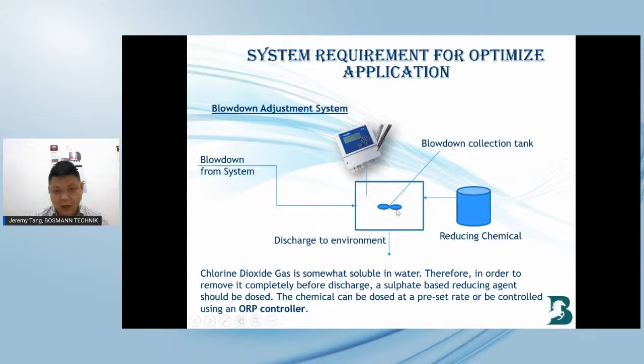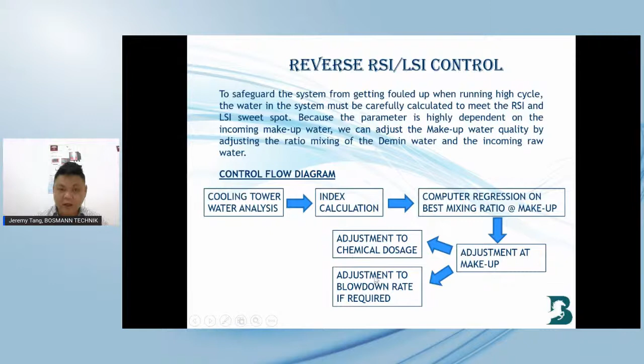Okay, the last one, to safeguard the system from getting fouled when running high cycle, the water in the system must be carefully calculated to match the RSI and LSI sweet spot, because the parameters are highly dependent on the incoming makeup water. So we must adjust the makeup water quality by adjusting the mixing ratio of the demineralized water and the incoming raw water. Okay, this is the control flow diagram. We do the cooling water tower analysis and calculate all the indices, and then we adjust the makeup water, the ratio of the raw makeup water and the demineralized water. After that, we calculate the chemical dosage and the blowdown rate required.